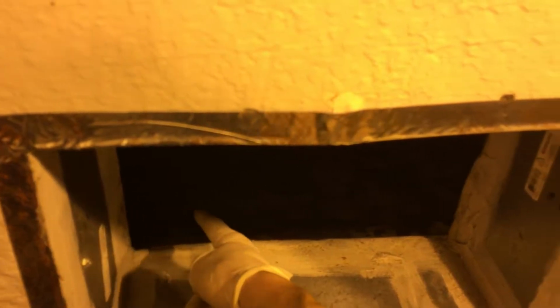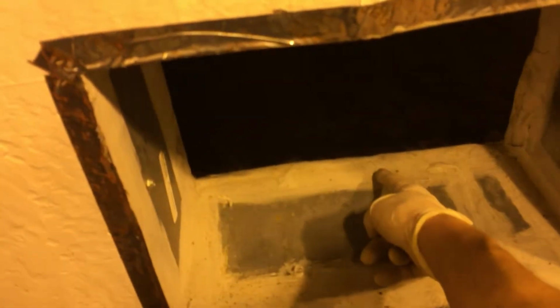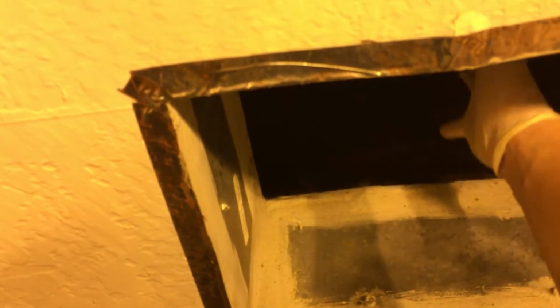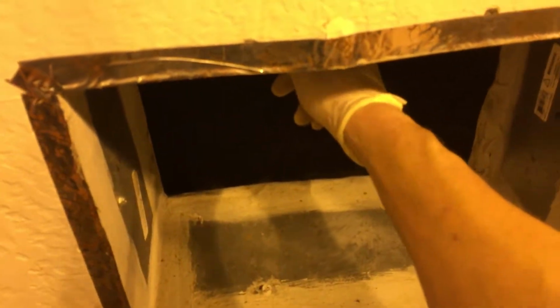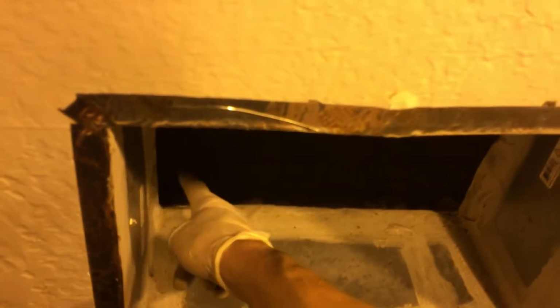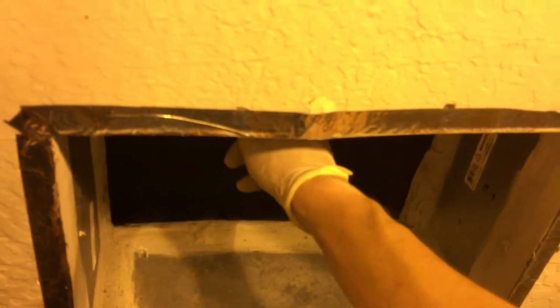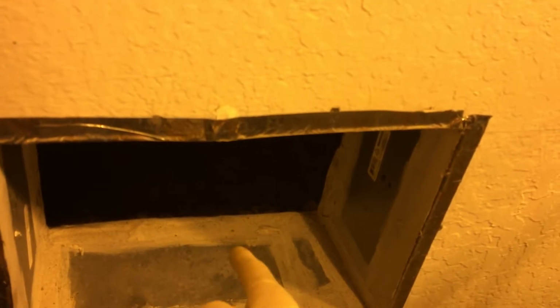This is 12 inches from here to here, and 14 inches from here to here. This is 14 inches by 12 inches on a 5-ton system. Now we pan up. There's only one outlet to this 5-ton vertical air handler on the other side of this wall. That's a 12-inch duct. So you've got all 5 tons going through 12-inch ducting.